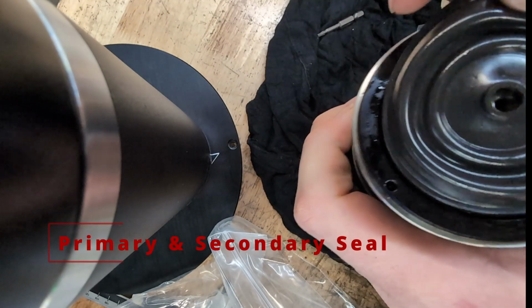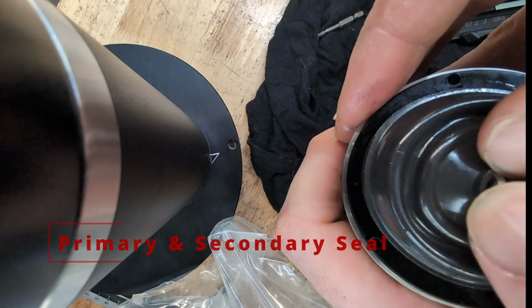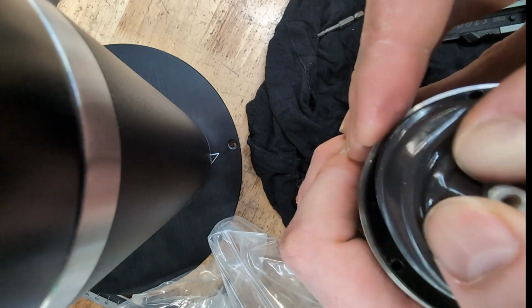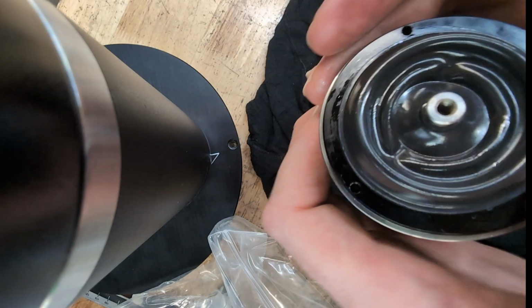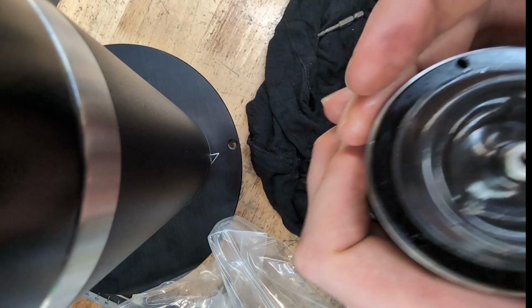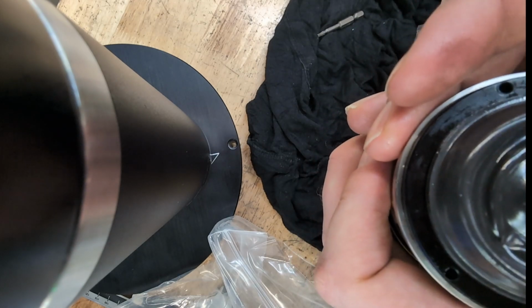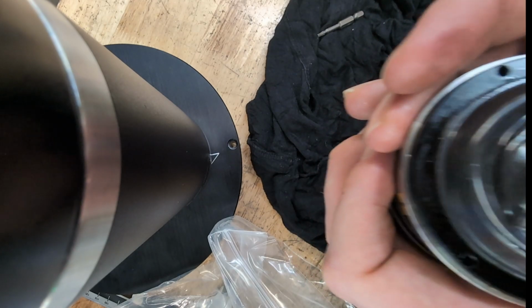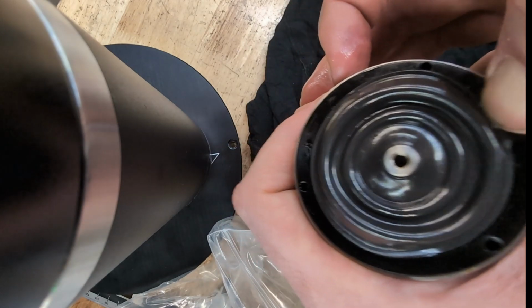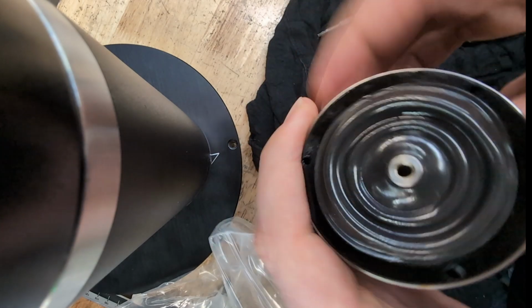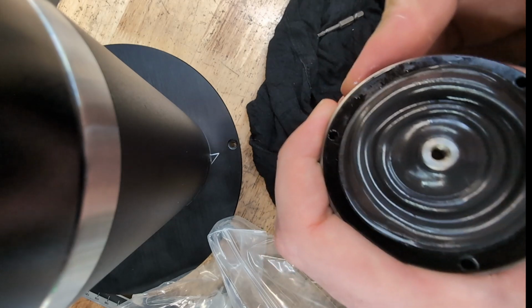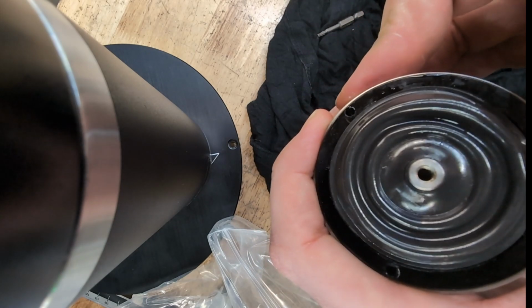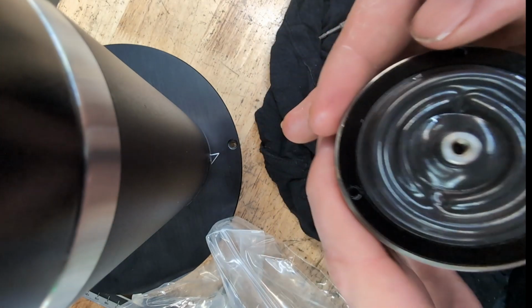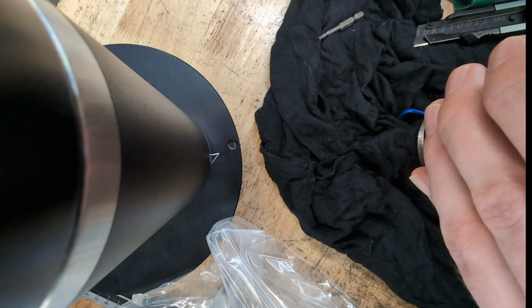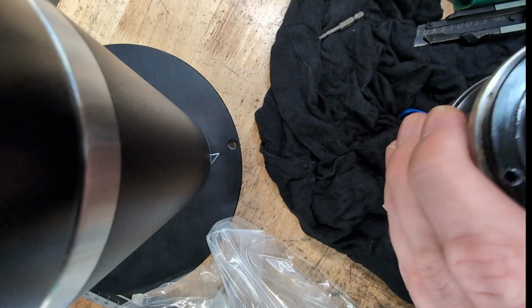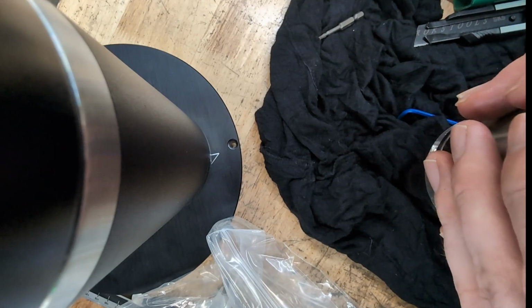Primary and secondary seal installation. Now we move on to installing the first of the 2 critical liquid seals that protect the probe from coolant. When installing this primary seal, pop one side into its groove, then work your way around the diameter. Crucial tip here, always push radially back towards your starting point as you feed it in. You want to make sure you aren't creating tension or stretching the rubber band as you go. If you don't do this, you will end up with too much excess seal to push in at the very end. Once it's all the way around, give it one final push down along the entire perimeter to make sure it is perfectly seated.